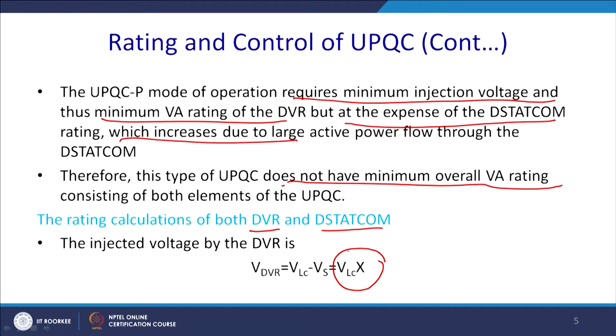The rating calculations of the D-STATCOM and DVR are done below as done in case of the UPQC-Q. So, the DVR rating will be VLC minus Vs, that is, you can write VLC into the fraction of the sag or swell. Thus, the overall VA rating of the DVR will be given by V DVR into Is, that is VLC into IL into cos phi, where Is and IL are the supply and the load current respectively, and cos phi is the load power factor. So, it will depend on the load power factor. The current rating of the D-STATCOM, I_DSTATCOM, should be square root of IL square minus Is square plus x, that is a fraction of the sag, x IL cos phi square.